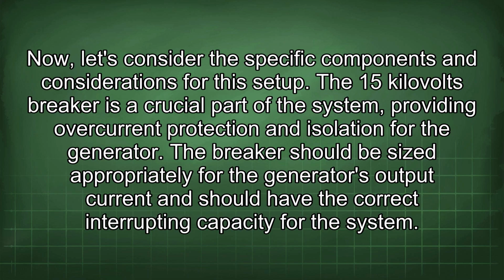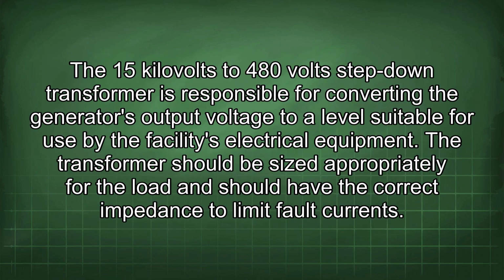Now let's consider the specific components and considerations for this setup. The 15 kilovolts breaker is a crucial part of the system, providing overcurrent protection and isolation for the generator. The breaker should be sized appropriately for the generator's output current and should have the correct interrupting capacity for the system. The 15 kilovolts to 480 volts step-down transformer is responsible for converting the generator's output voltage to a level suitable for use by the facility's electrical equipment.